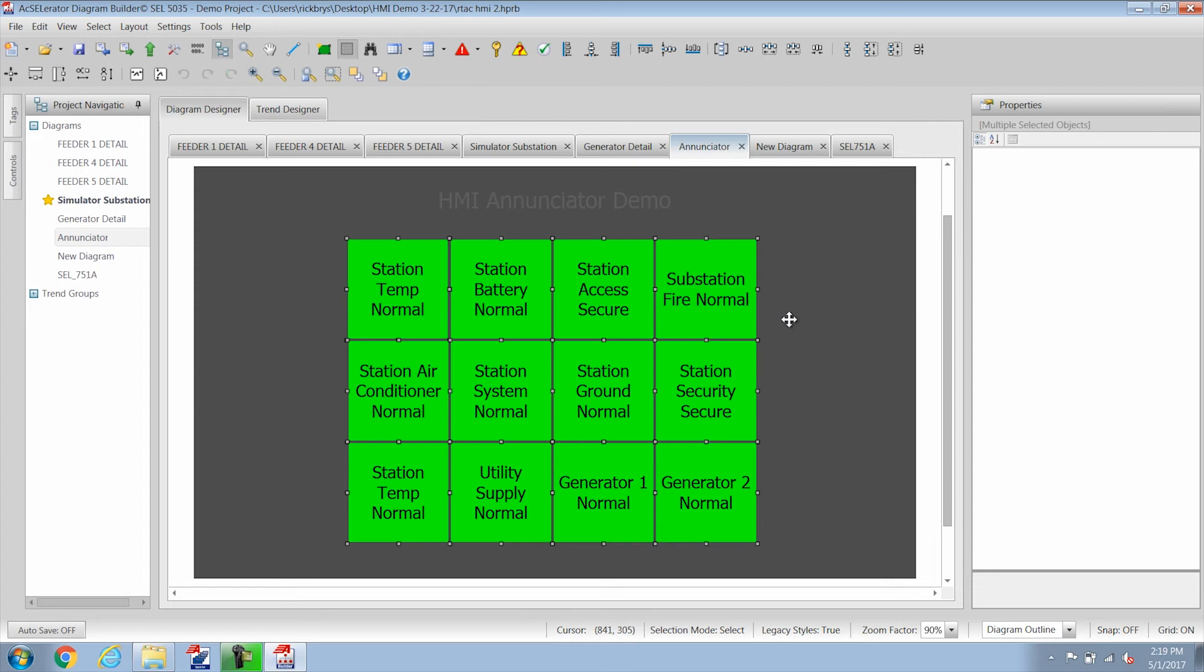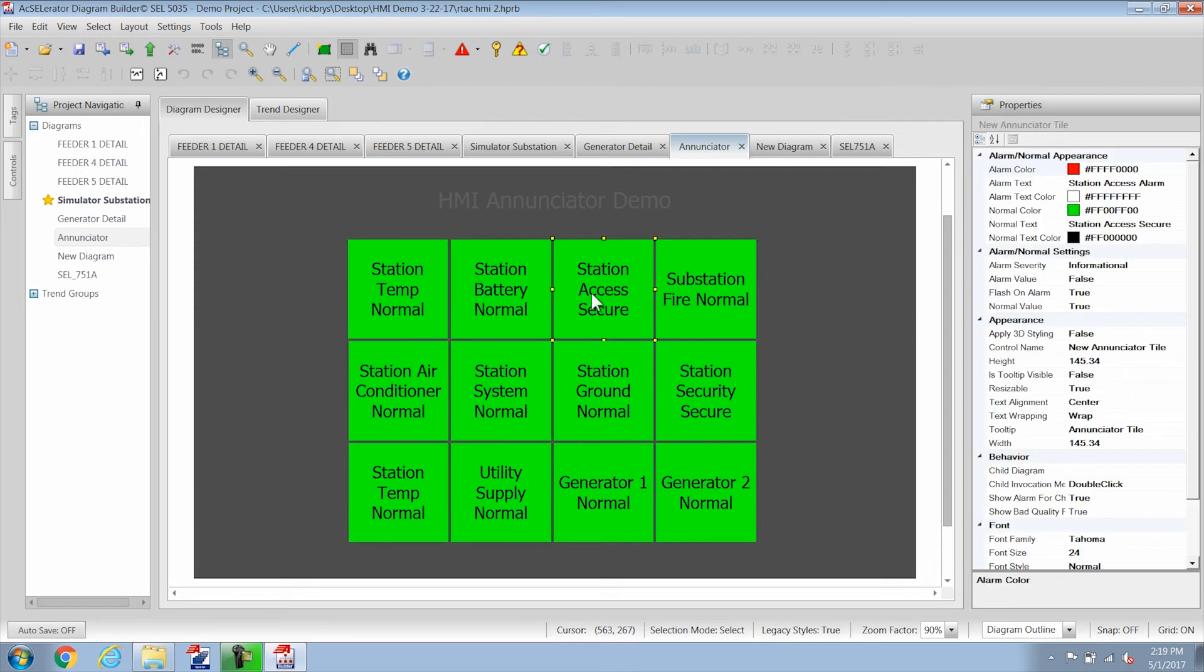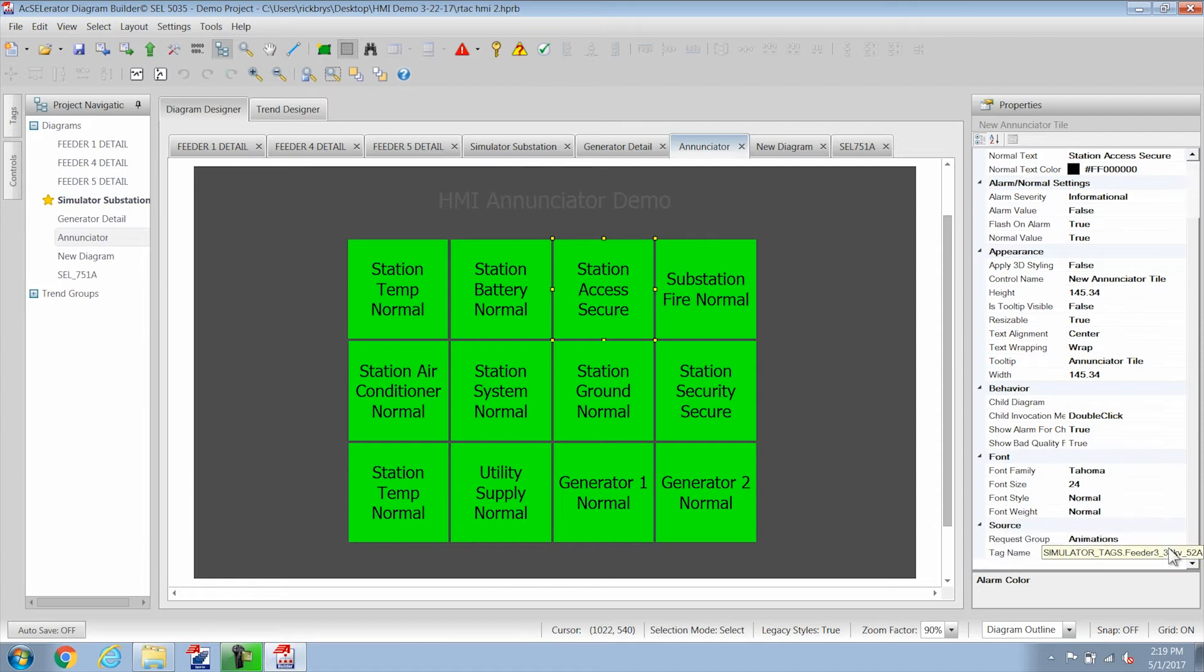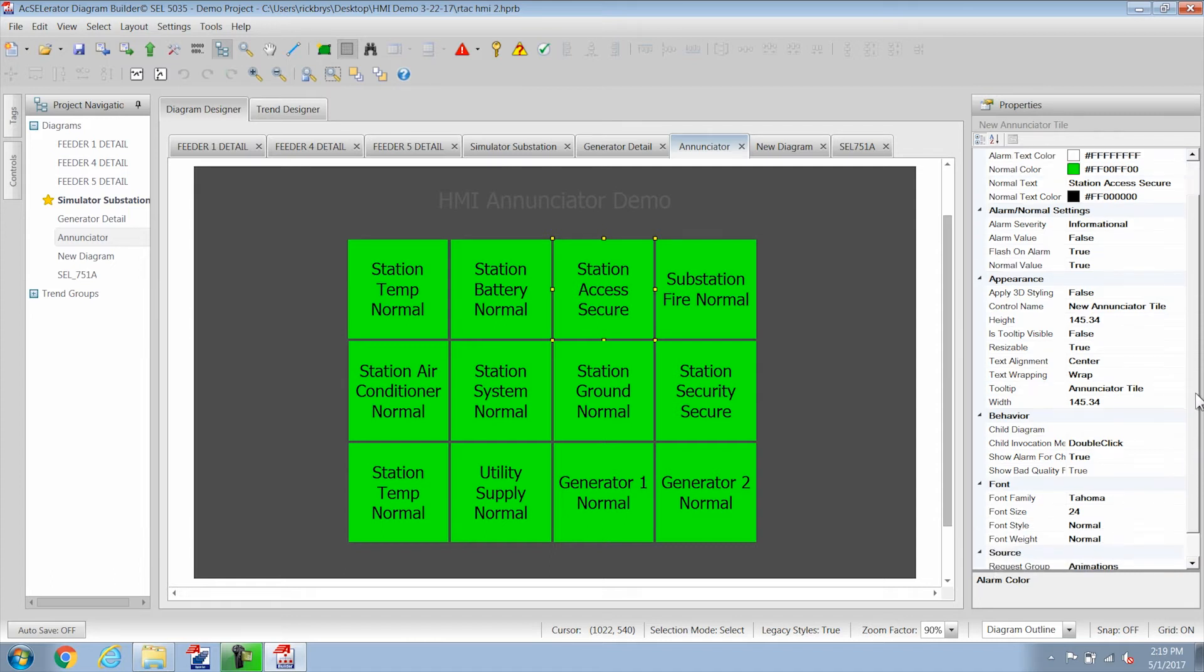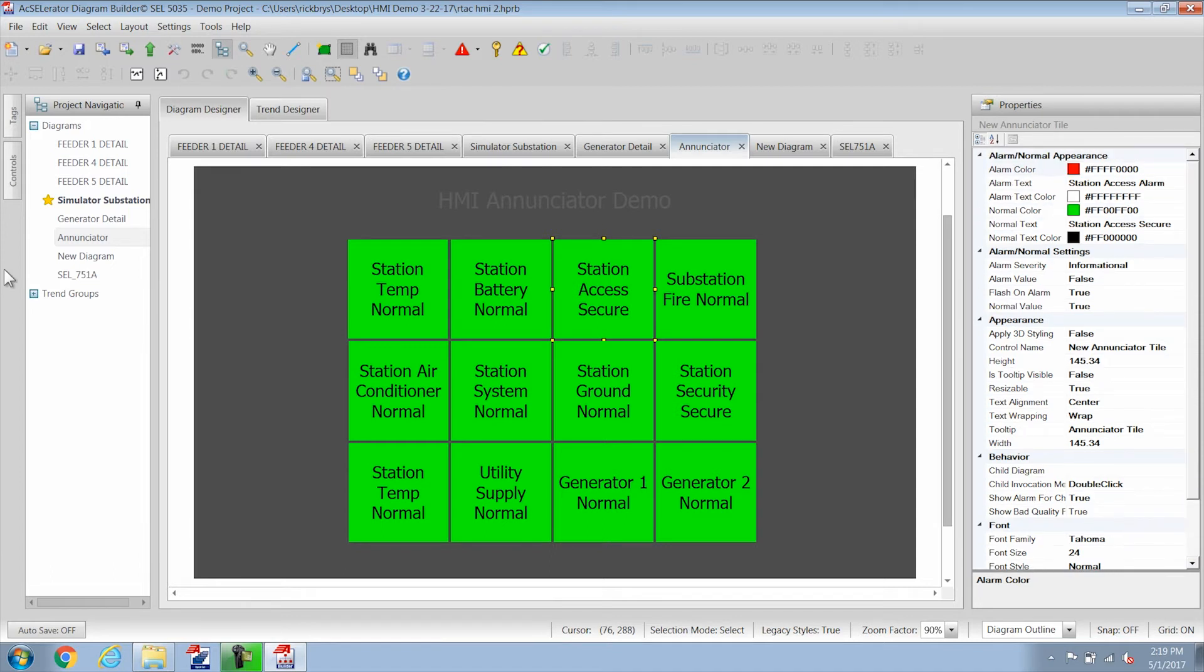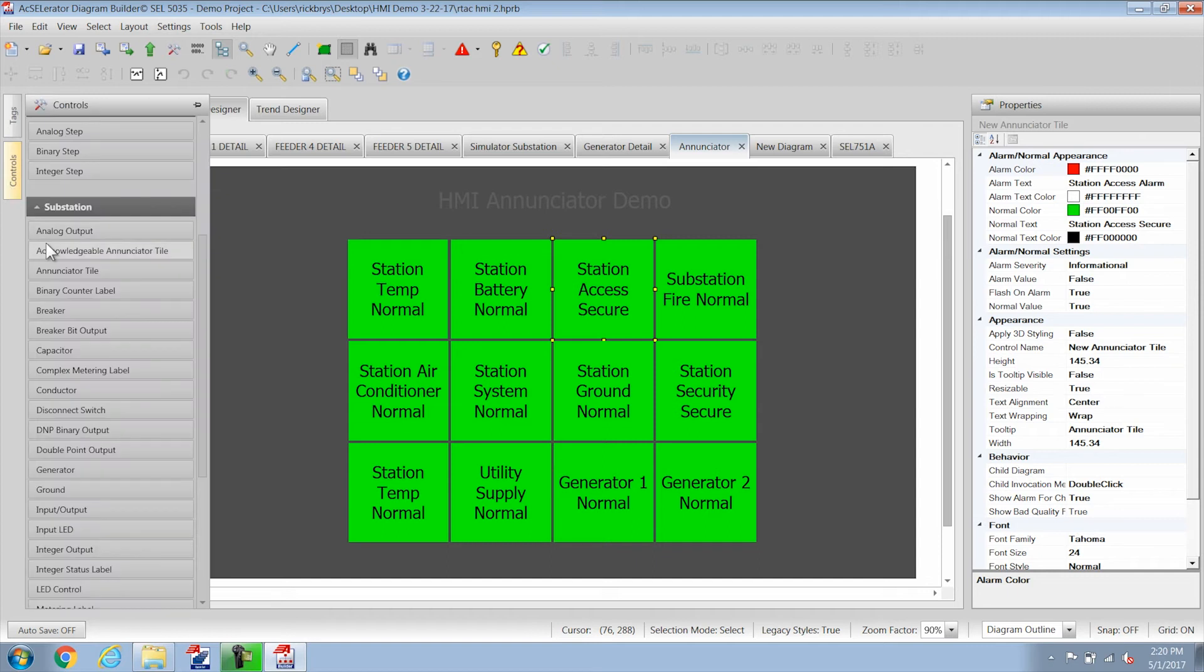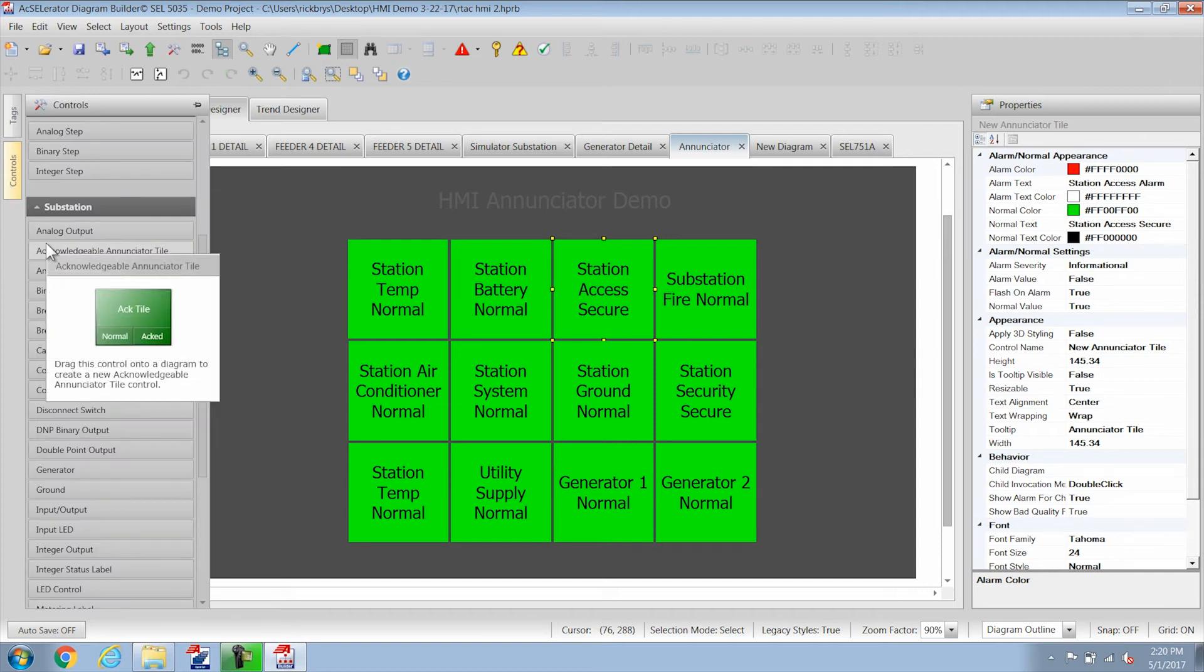And they can flash based on a status point. So here I can change the tag name of that status point and also change the color and what they're going to do. We have acknowledgeable annunciator tiles as we see here that you can acknowledge them so when they start flashing because they're in alarm you could acknowledge them.